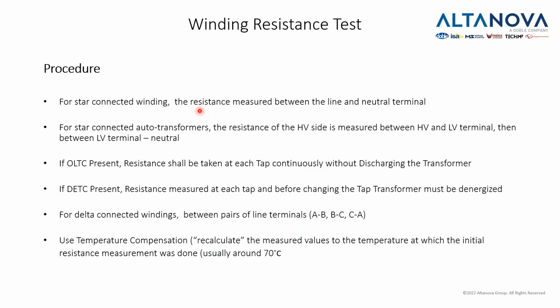And when we measure a star connected winding, the resistance measured is between line and neutral, and for delta it is between two phases. If we have auto transformers, the resistance of the high voltage side is measured between high and low voltage, and then the low voltage is measured between low voltage and neutral. We also need to use temperature compensation, because very often when we evaluate the results, we will see numbers which were obtained in the factory at a much higher temperature, usually 65, 70, 75, 80, 85, depending on the producer. And we are measuring right now, and it's maybe 15 or 5 or 25 degrees.